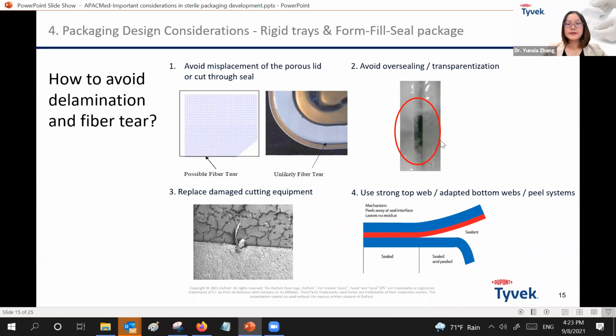And second, avoid oversealing. This is obvious. With oversealing, the seal strength may increase, but with increased seal strength, it's easy to have delamination or fiber tear. And third, it is also important to replace damaged cutting equipment, because a cracked edge caused by damaged cutting equipment could be a potential initiation of fiber tear or delamination. So always using sharp and undamaged cutting equipment is very important. And lastly, a non-adapted peel system can also lead to bad peeling behavior. So make sure that you use an appropriate sealant either on the Tyvek or on the film side to allow for good peel performance.